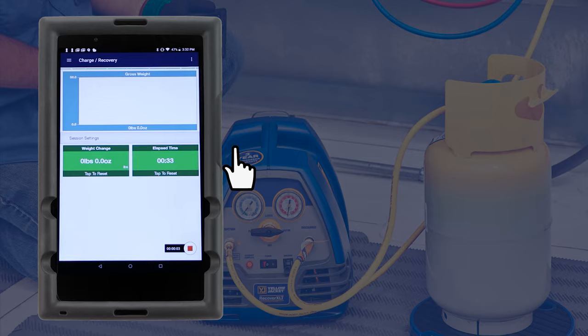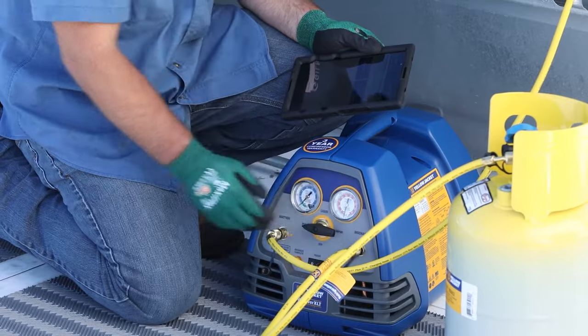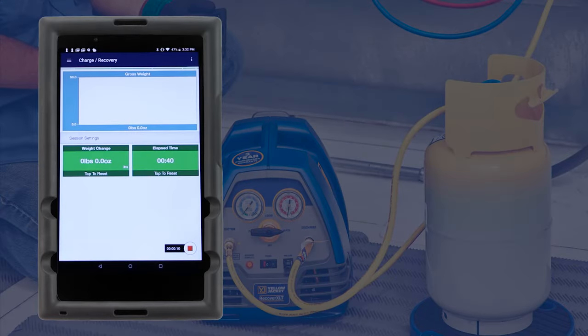Now the tank valve can be opened and the recovery machine can be powered on to start the recovery. In line graph mode, as the scale weight changes, the vertical axis of the graph will repopulate to show the full range of scale readings as the weight increases.